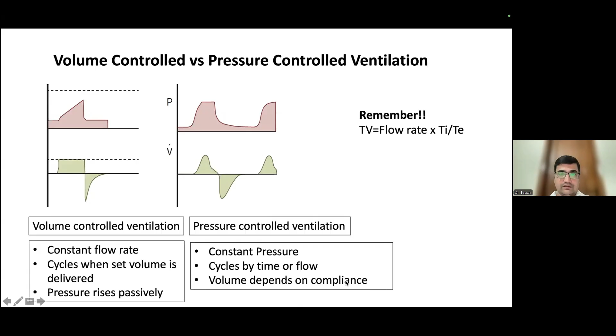So this slide is also showing the same concept that I discussed in the previous slide. The left one is showing the scalar waveform: pressure-time, volume-time, and flow-time for pressure control ventilation, and similarly for volume control ventilation. You can see that in pressure control ventilation, the flow rate is high during the beginning of the breath, that leads to early achievement of the PIP, and then the flow rate decreases in a descending ramp that leads to maintenance of the PIP during the inspiratory time, and then there is a negative flow which is marked by the expiration.